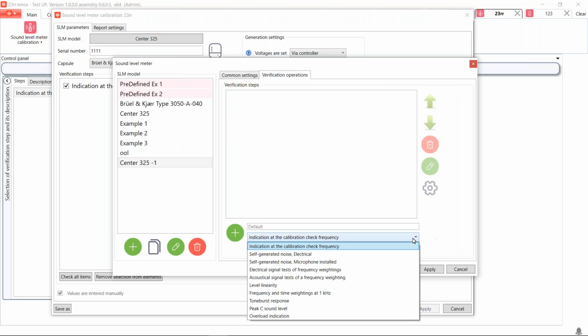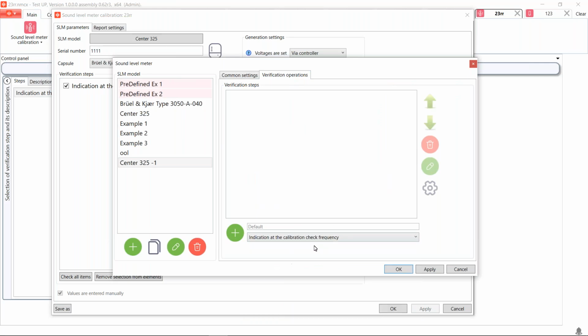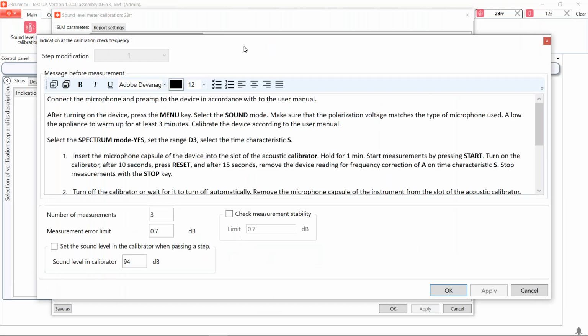So as I said, these verification steps were created in accordance with the standard for sound level meters calibration. And for this sound level meter, unfortunately, we can show you only one step, and it is indication at the calibration check frequency. So let's add it. We need to click on the green plus. And by clicking on the button, you will see a window where you can enter the way the procedure of calibration should be performed for the sound level meter under calibration. And in the window, you can see the instruction to perform this step of calibration in accordance with its description in the standard. This keeps the correct procedure always visible to the user, streamlining your workflow.